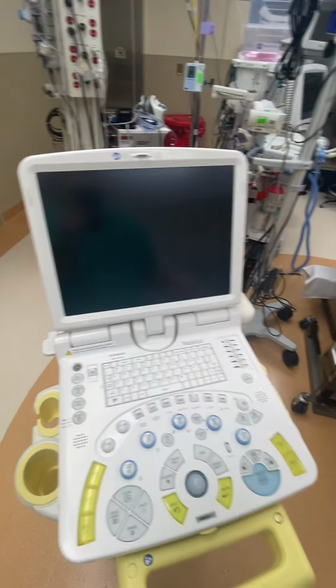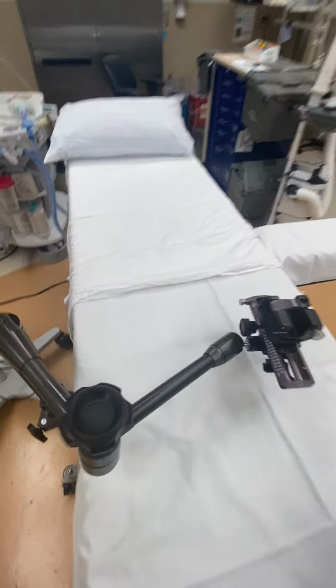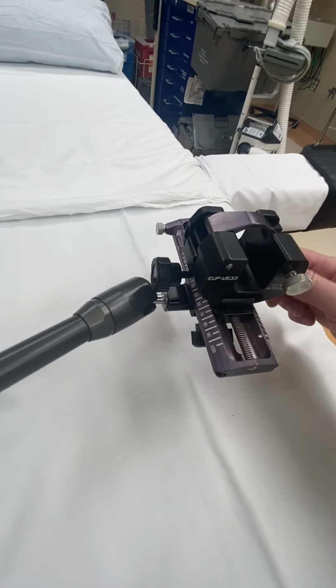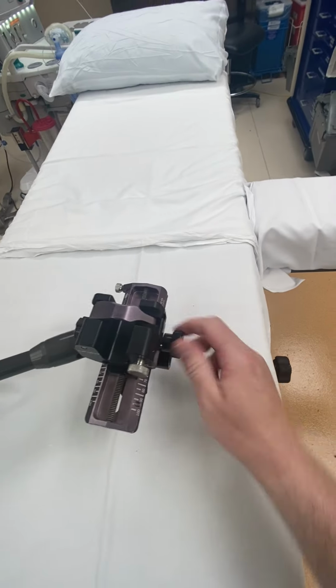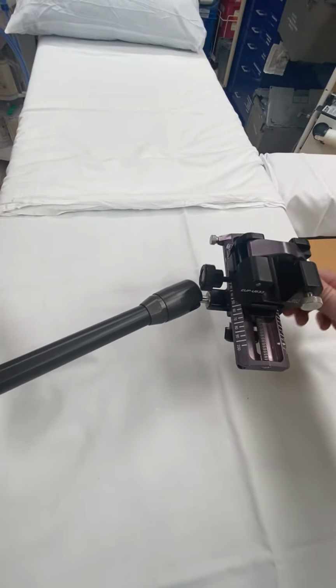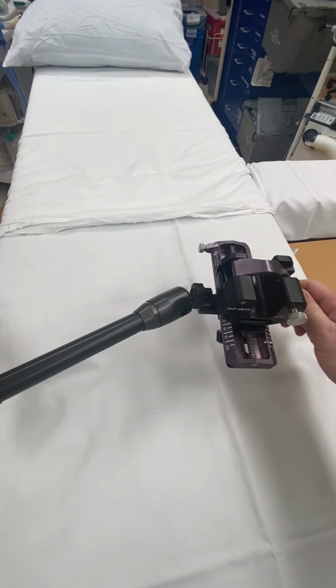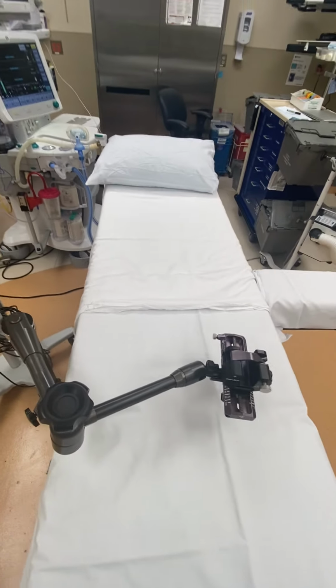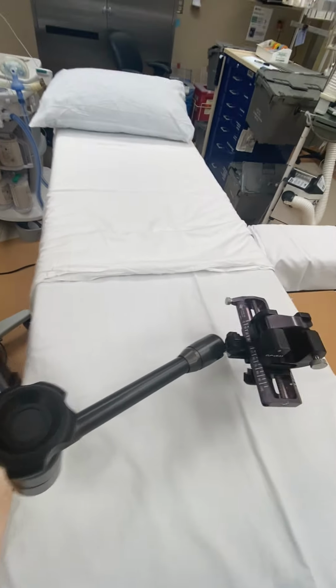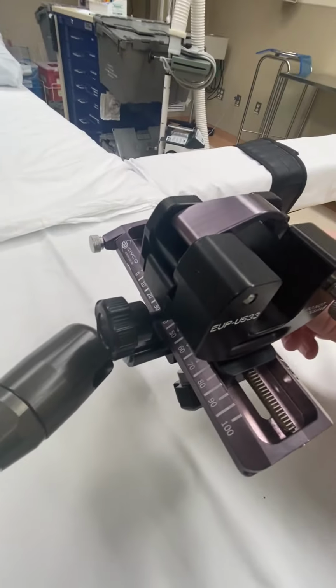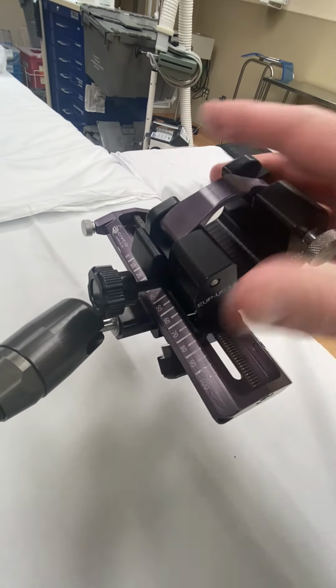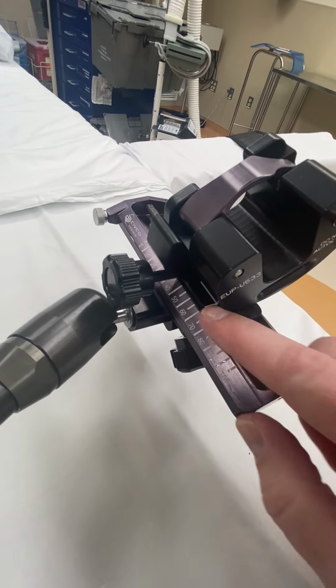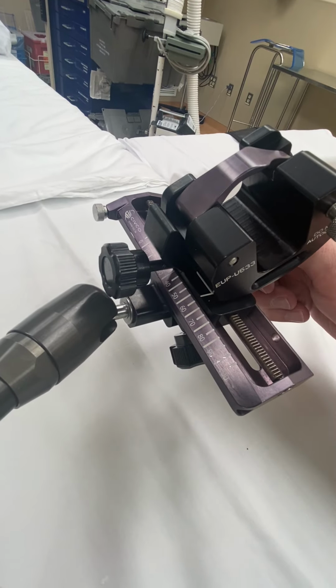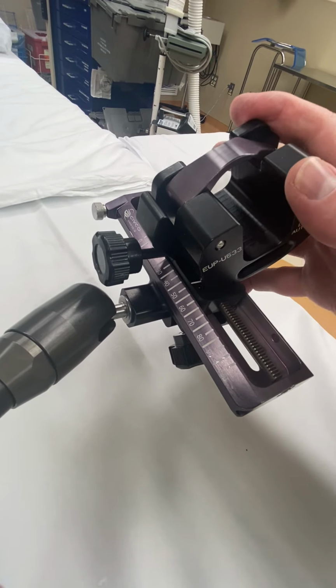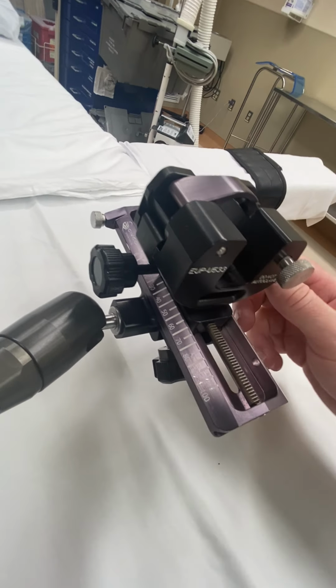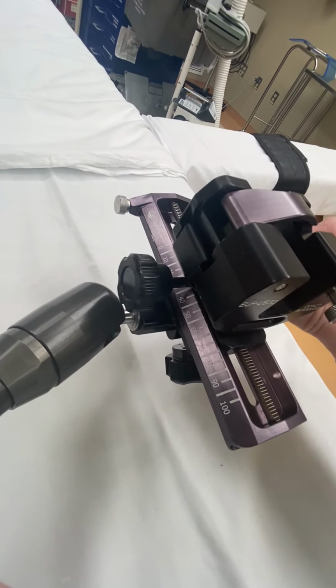Depending on the view, they're going to have to step in and step out. The stepping is the knob here. By turning this knob, which is on both sides, they can go in and out. Basically they have to go in and out whenever they step to put the crystal under the prostate. The other videos go into more detail about that. When you're using the stepper though, you want to make sure you start at the 50. It's hard to see here, but this white line under the cradle needs to be at the 50 when you start, meaning when you insert the probe, because that's in the middle of the stepper, so they have equal movement in and out.